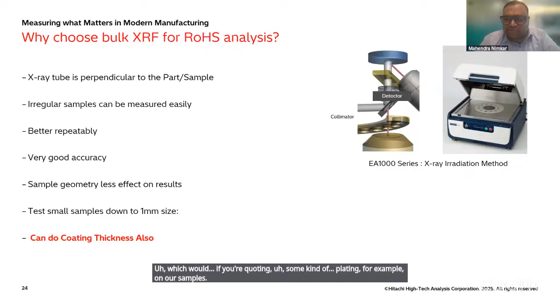So the bulk XRF, or we call it the benchtop XRF, is very good, though it is slightly costly, it has very good accuracy. Repeatability is very good, and at the same time you can do very small samples also, small fasteners. If you want to do, let's say, ink or something like that, you can do it. I'm sure you know that even the ink which you print on your product has to be RoHS compliant. And of course, you can also do some coating analysis, if you're coating some kind of plating, for example, on your samples. So coating thickness measurement is also possible on a benchtop XRF.